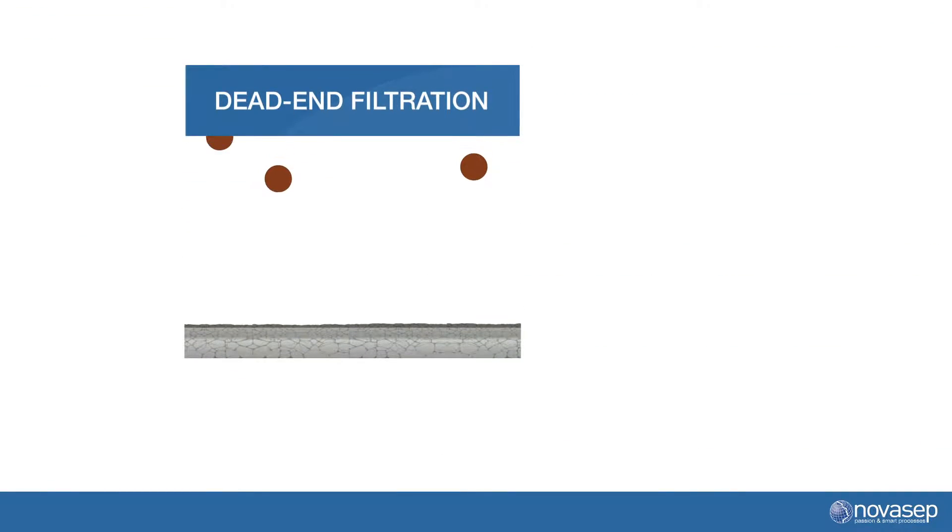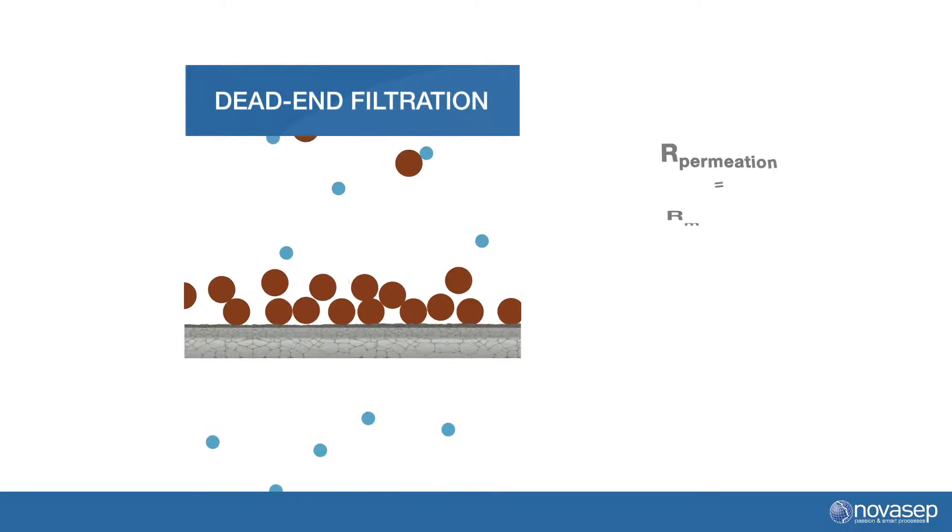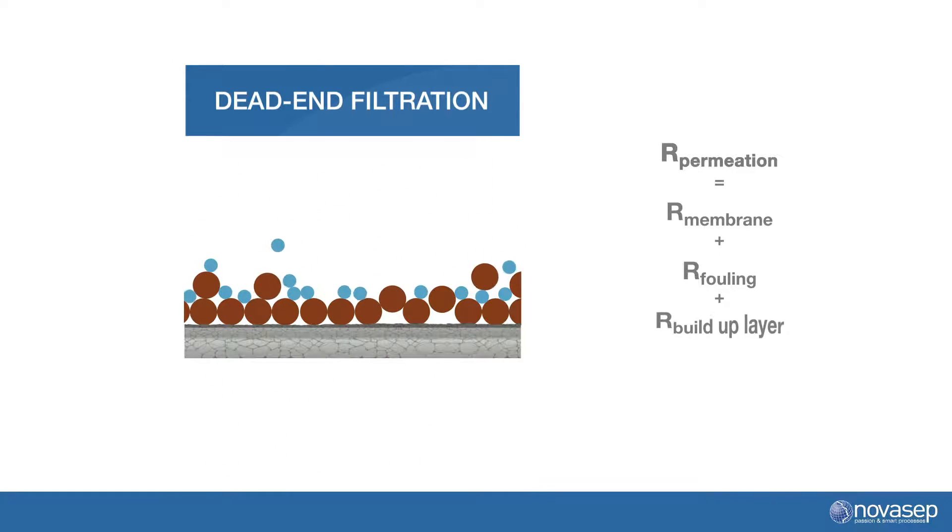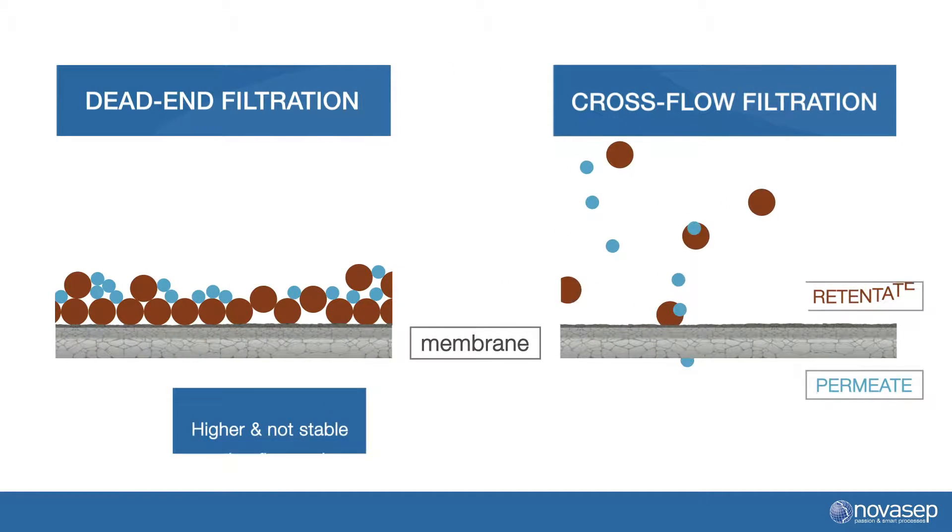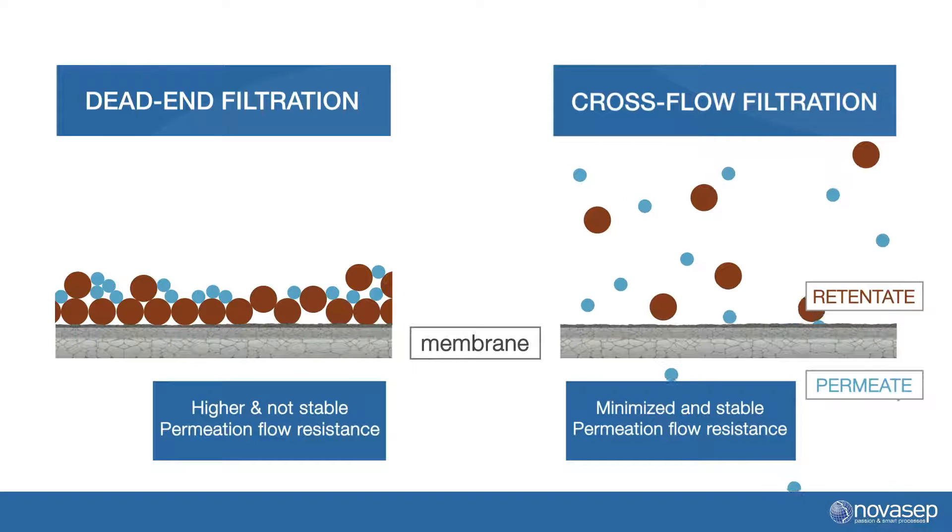Because it is what differentiates cross-flow filtration from dead-end filtration. The driving force of the permeate through the membrane is the difference of pressure between the two sides of the membrane, called the TMP or transmembrane pressure. Resistance to the permeate flow is a combination of the ceramic layer of the membrane itself fouling in the membrane and a build-up of a clogging layer on the feed retentate side of the membrane. The whole purpose of having a cross-flow is to erode continuously this clogging layer and get as little resistance to the flux as possible.